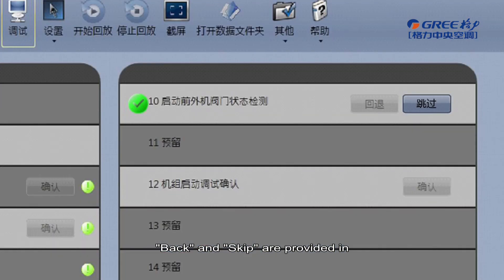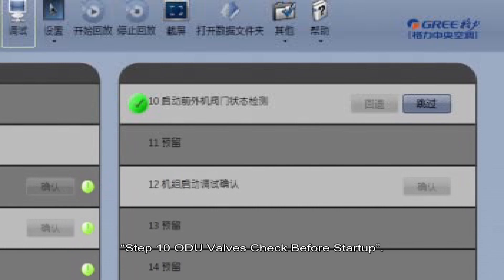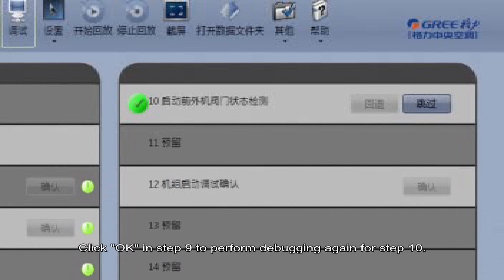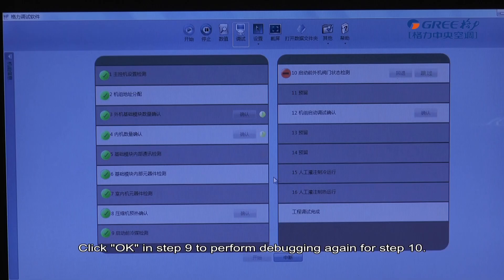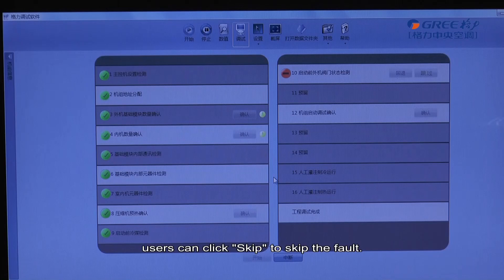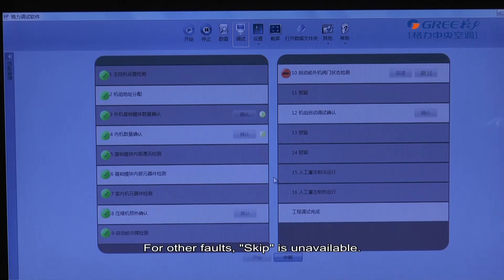Back and Skip are provided in step 10, outdoor unit checks before startup. When step 10 is abnormal, click Back to return to step 9, then click OK in step 9 to perform debugging again for step 10. If a usage fault occurs in step 10, users can click Skip to skip the fault. For other faults, Skip is unavailable.